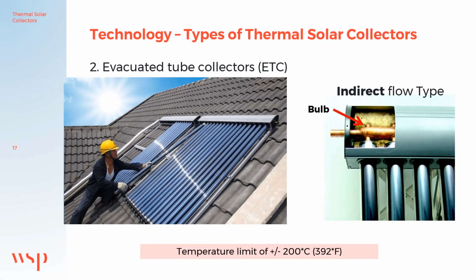ETCs typically have a liquid out temperature of around 200 degrees C or 392 degrees Fahrenheit, and are more expensive than flat plate collectors. ETC technology is proven technology, and the collectors are readily available. There are no moving parts in these collectors. It's also important to note that the individual tubes are lightweight, easy to install, and can be replaced easily if damaged.